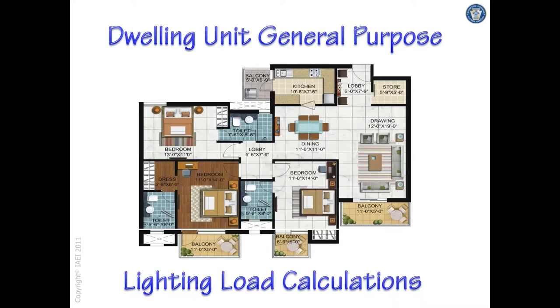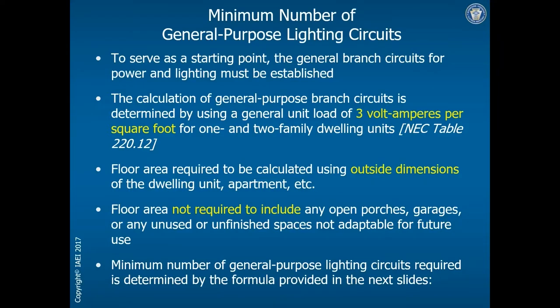Here's another calculation that we do quite often: the general purpose lighting load for a dwelling unit. This is how we determine the minimum number of general lighting circuits for a dwelling unit — the general lighting circuits that supply power to switches, lighting, and receptacles in dens, bedrooms, and similar spaces. We have a table in the 2017 code, and there was a change in the 2020 code we'll look at shortly. It doesn't change the calculation, but it does change where we find these rules.